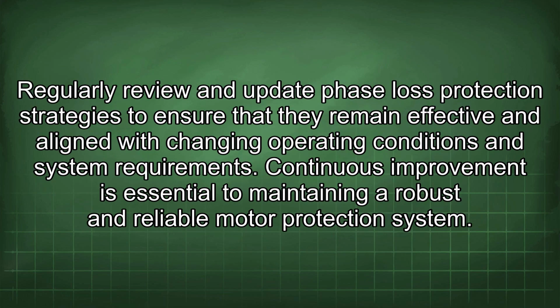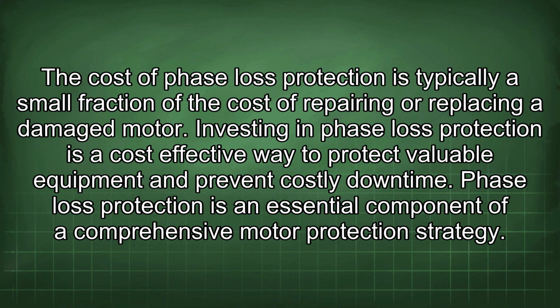Regularly review and update phase loss protection strategies to ensure that they remain effective and aligned with changing operating conditions and system requirements. Continuous improvement is essential to maintaining a robust and reliable motor protection system. The cost of phase loss protection is typically a small fraction of the cost of repairing or replacing a damaged motor. Investing in phase loss protection is a cost-effective way to protect valuable equipment and prevent costly downtime.